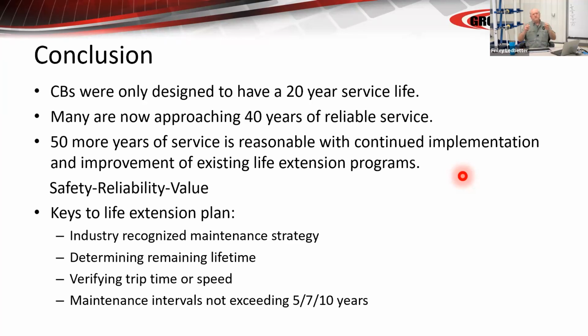So as a maintenance professional, you need to make sure your protective relays, your trip circuits, your CTs, your PTs, that the trip circuit between them and the breaker will operate. Finger the relays, operate the breakers offline, and make sure the system works. Push current through the system, make sure the relays operate, make sure the trip circuit is intact, finger the relays, make sure the breaker trips, make sure it sounds right, runs right, acts right, and smells right.